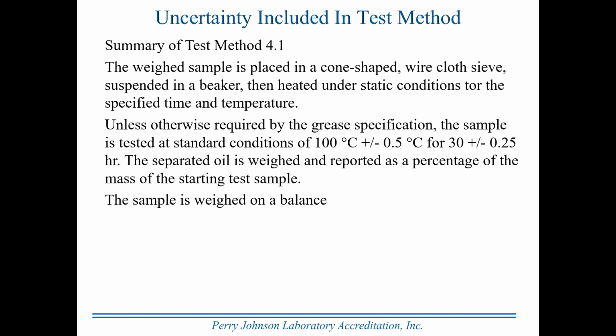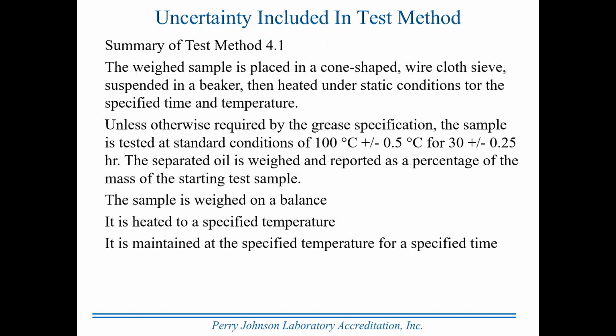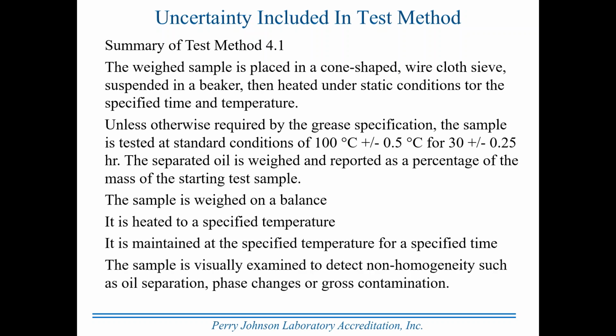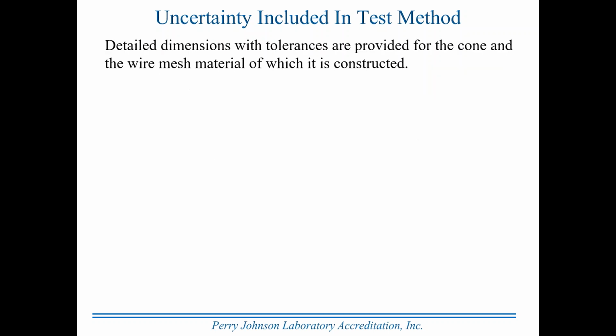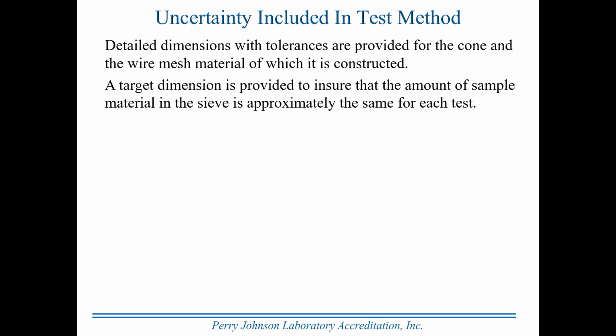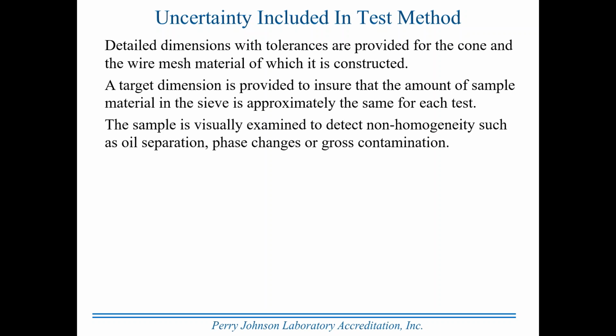The sample is weighed on a balance. Makes sense so far. It is heated to a specified temperature. It is maintained at that specified temperature for a specified time. The sample is visually examined to detect non-homogeneity, such as oil separation, phase changes, or gross contamination. Detailed dimensions with tolerances are provided for the cone and the wire mesh material of which it is constructed so that they can be essentially similar from machine to machine, test to test. A target dimension is provided to ensure that the amount of sample material in the sieve is approximately the same for each test. Sample is visually examined to detect non-homogeneity, such as oil separation, phase change, gross contamination.